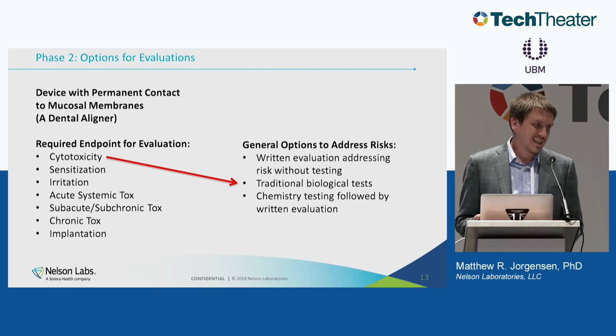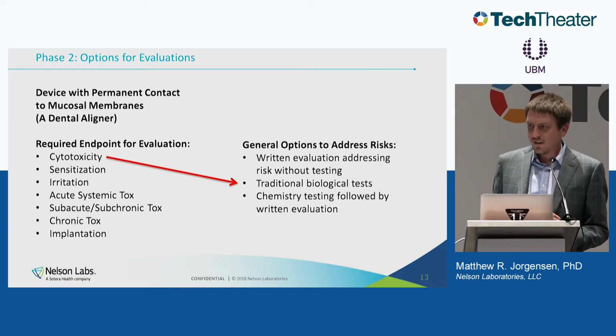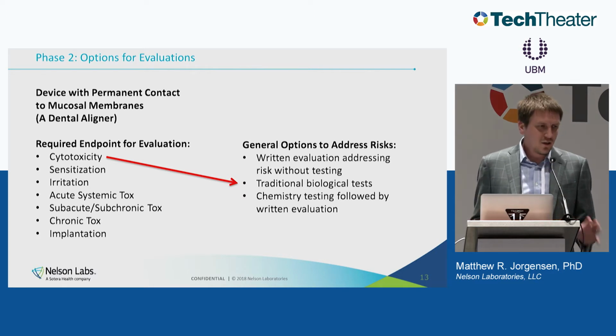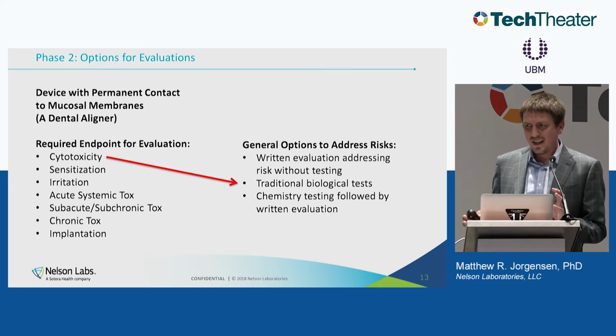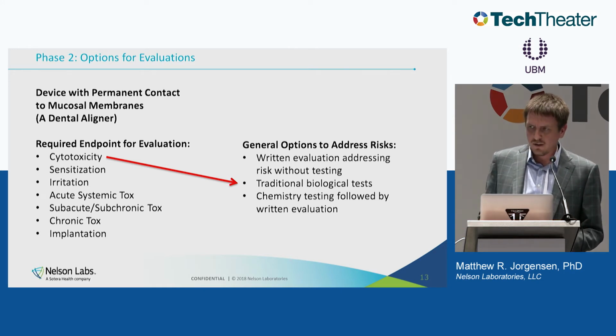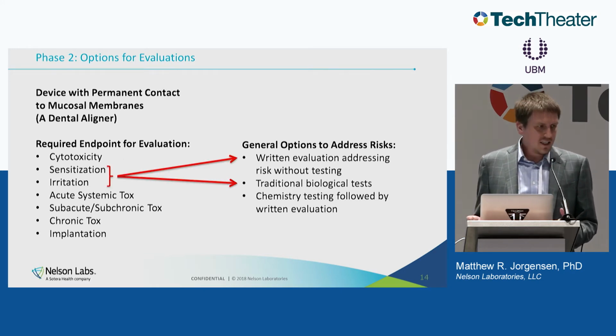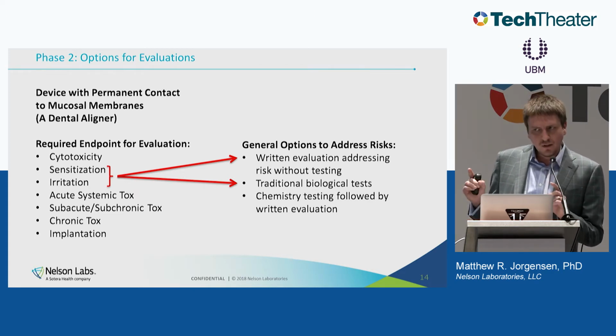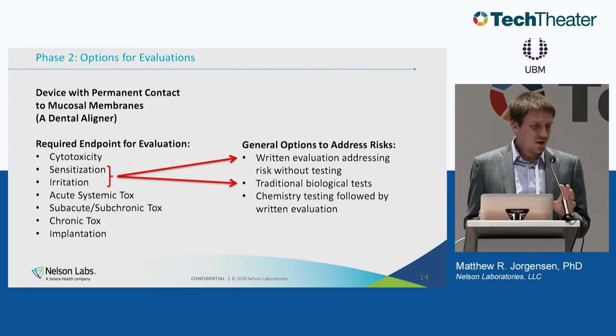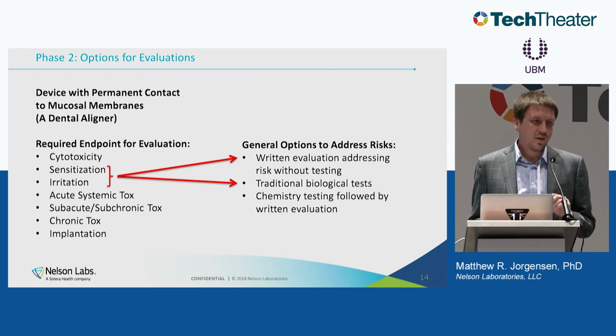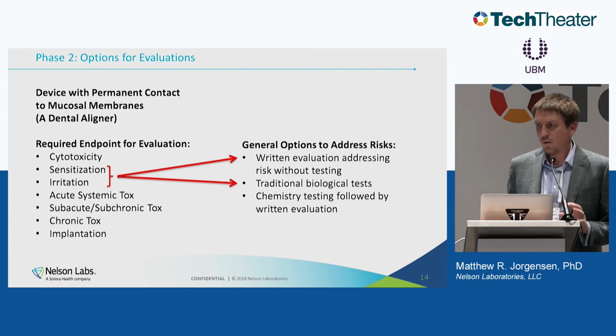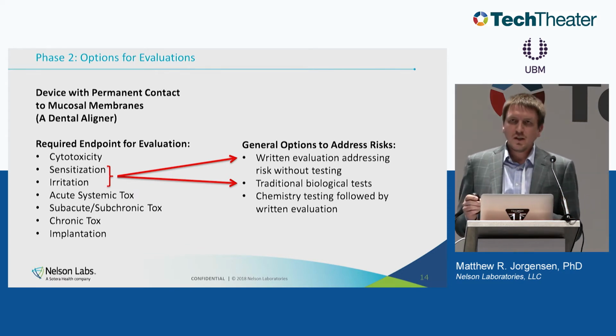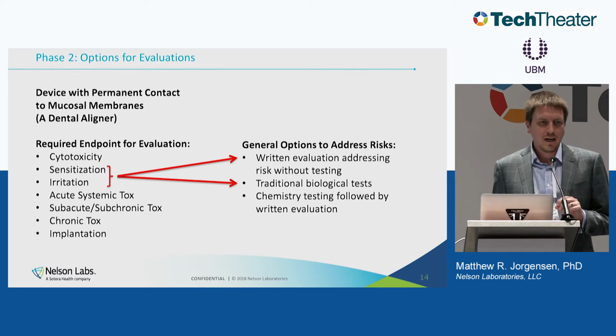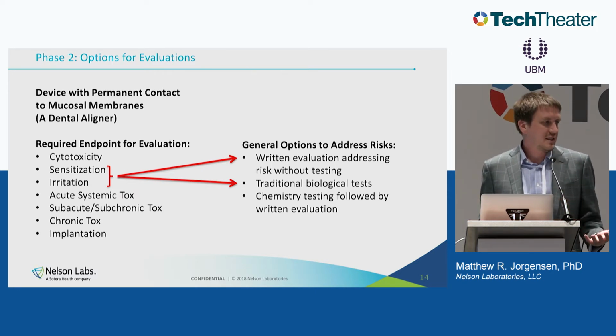okay, cytotoxicity testing, this is really inexpensive, it's pretty fast, it doesn't use animals, and the FDA does like to see it, so we'll basically always recommend the traditional test for cytotoxicity. For sensitization and irritation, we either always do the traditional test or just a written evaluation. And the written evaluation we found works really well if you have a very common, well-characterized material. So you can think of something like a well-known titanium alloy or a stainless steel alloy.